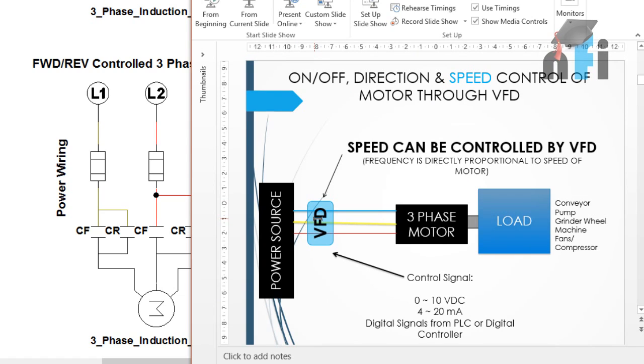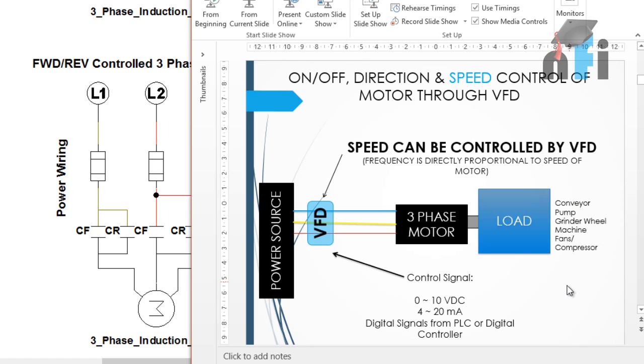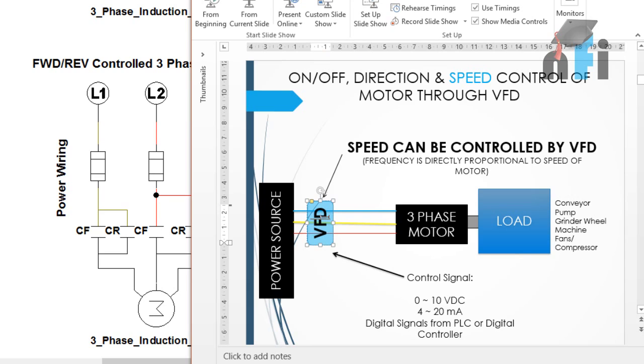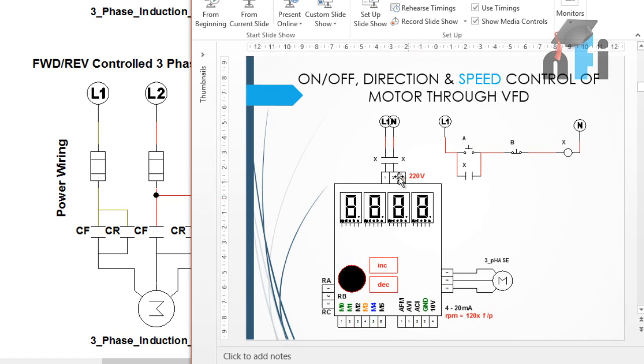We have also used a VFD (Variable Frequency Drive) in previous tutorials, which is typically used to control the speed of a motor. There are many applications requiring speed control - conveyors where you control speed depending on production rate, pumps to control pressure and flow, and grinding wheels. Speed control is an important factor. In VFD, the control signal is 0 to 10 volts, 4 to 20 milliamps, or a signal from a PLC. Operations like speed, direction, on/off, jog, and multi-speed can be controlled.